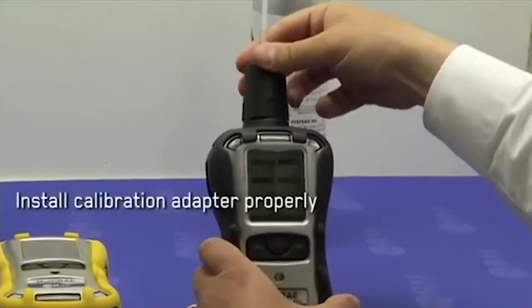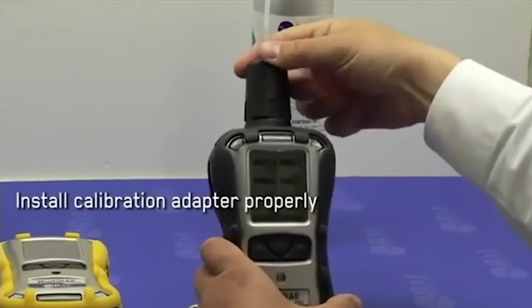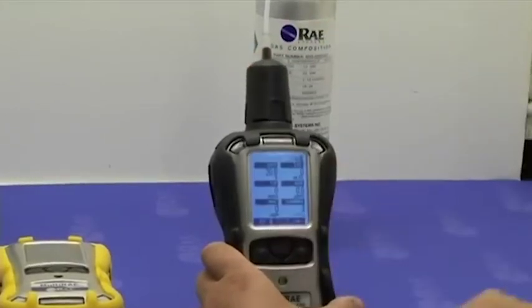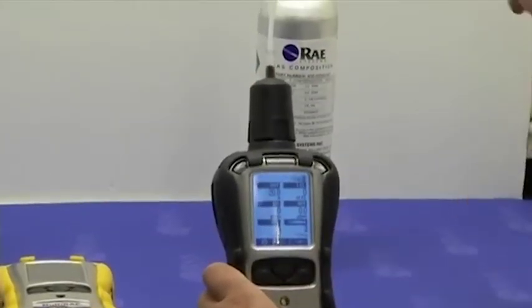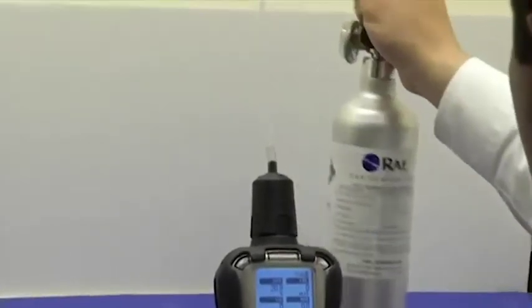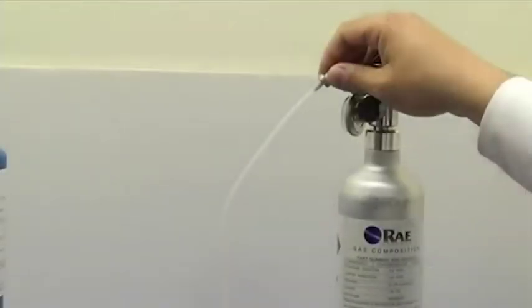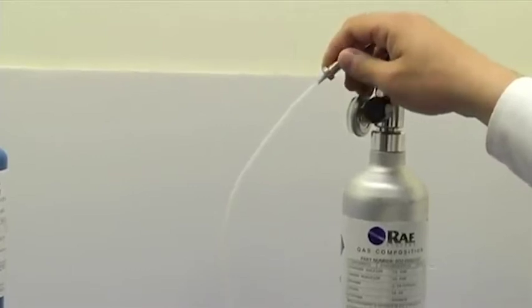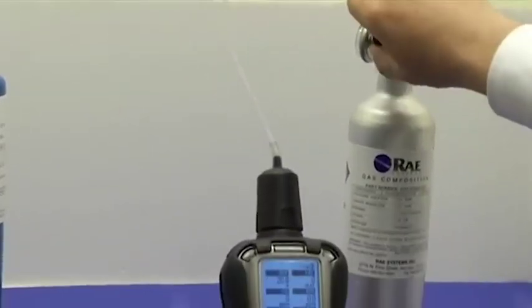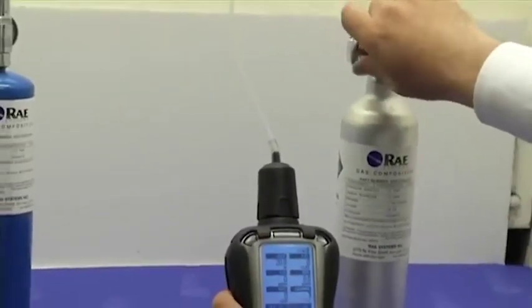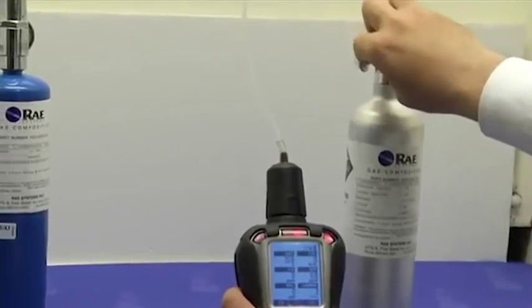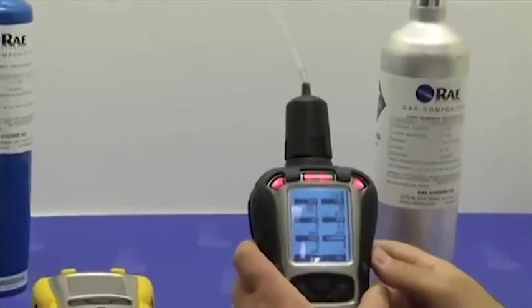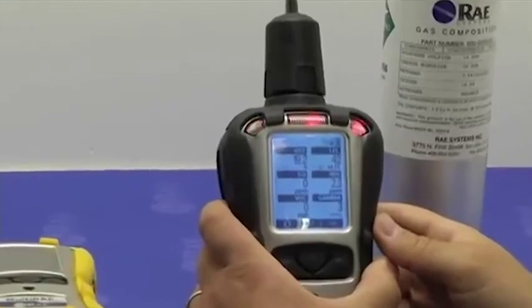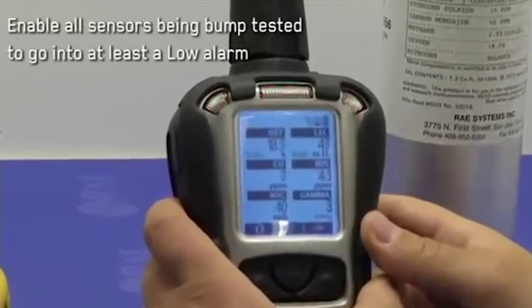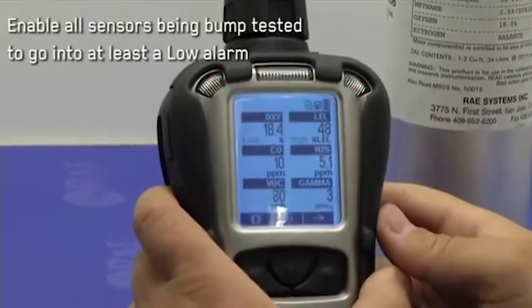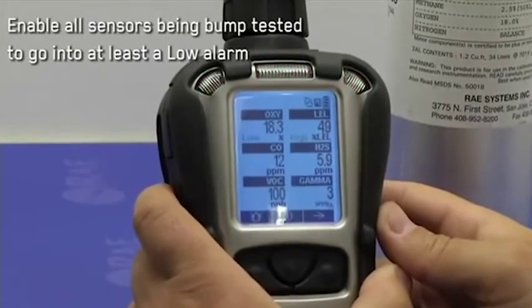When you install the calibration adapter, please make sure that it goes all the way down. Next, I'm going to connect the adapter to the gas cylinder, and we'll start the gas flow. What I'm looking for is for all the 4 sensors that are being bump tested to go at least into a low alarm.